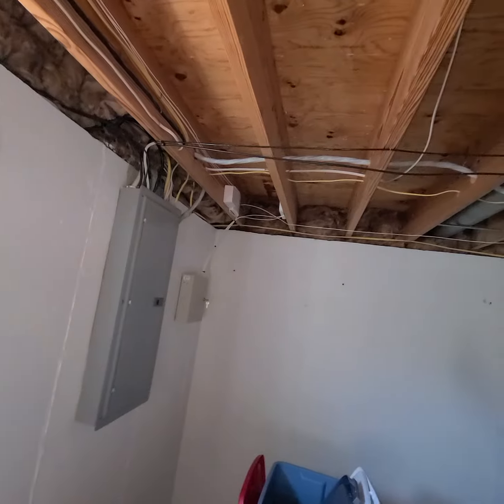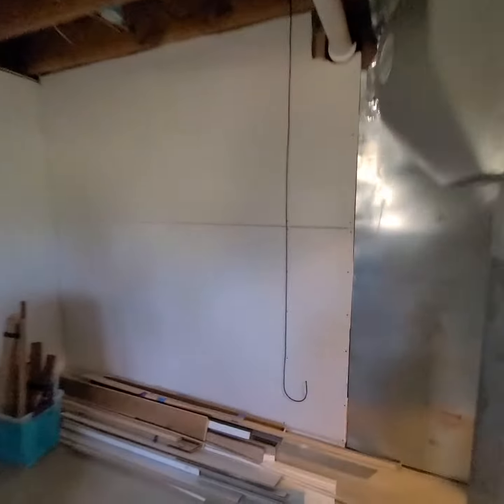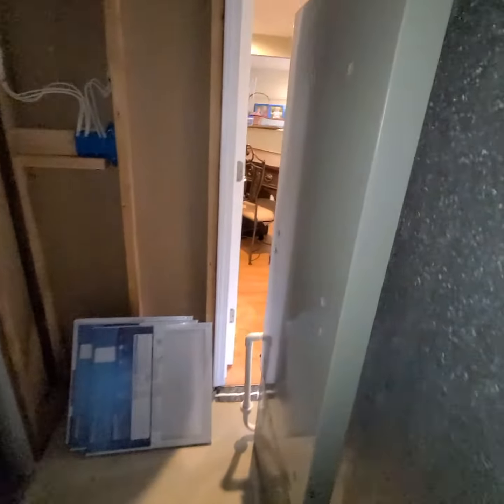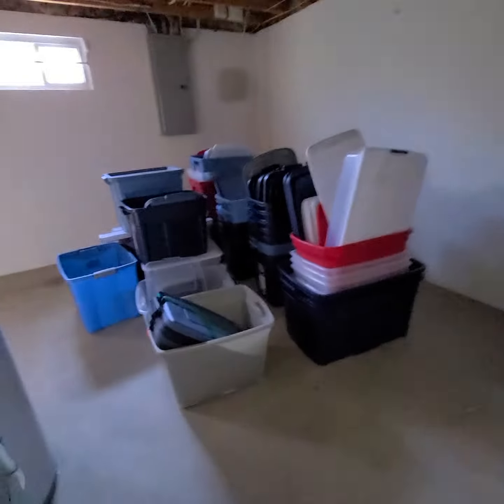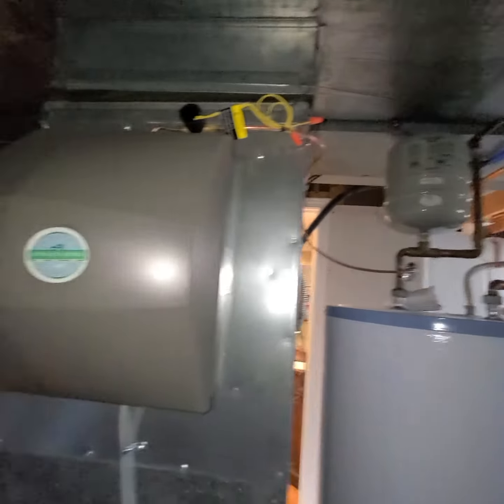We'll meter on and vent everything to the backyard through these joists for the water heater and for the new furnace. We'll also do a new humidifier. I was thinking about having the furnace facing this way so we can do a new return drop and a five-inch filter in a base — there's a ton of room between here, so we might just have to go back down the trunk line a little bit more to do that.